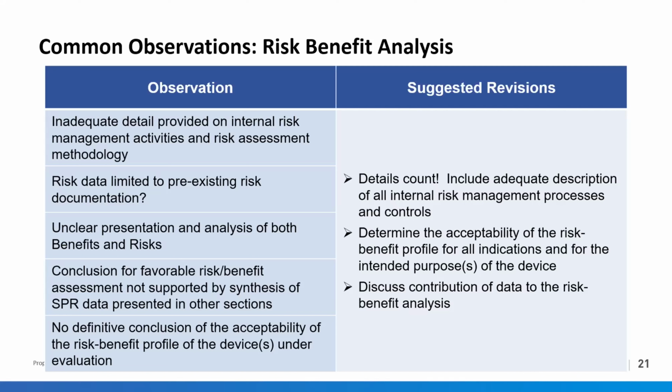The presentation and the analysis of both the benefits and the risks may be disorganized or difficult to follow, or worse than that, if your conclusion is not supported by the clinical data that you've presented in other sections, that's problematic. And then finally, we often see that there's not really a definitive conclusion statement that simply states the acceptability of the benefit risk profile on the device under evaluation. So we suggest that it's important to focus on those details.